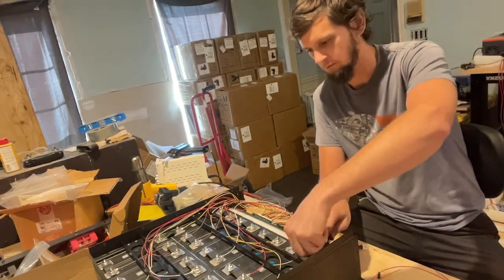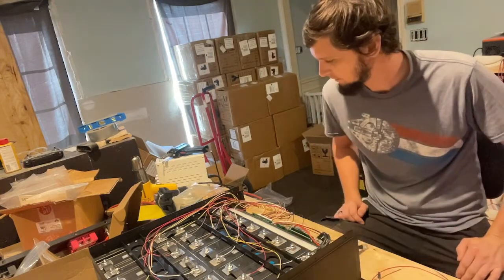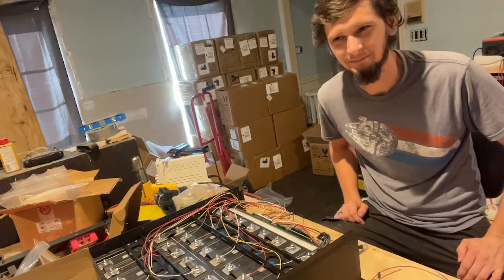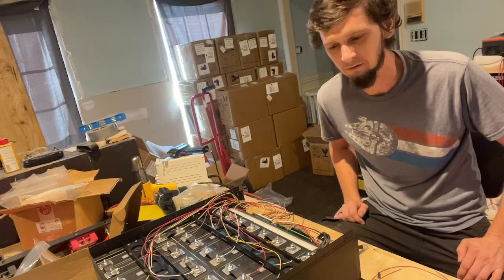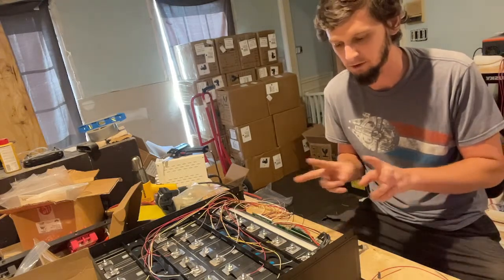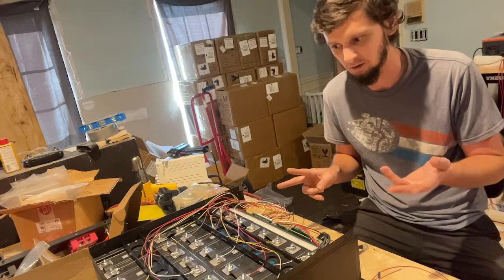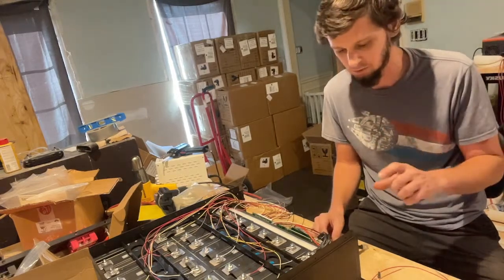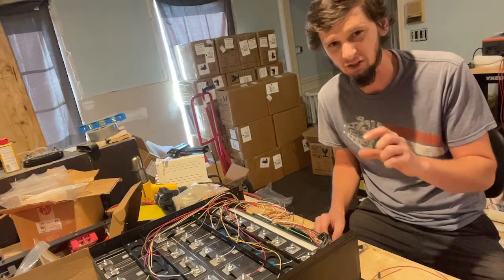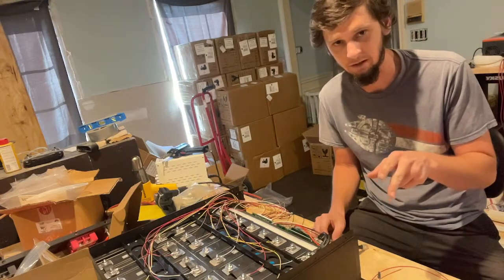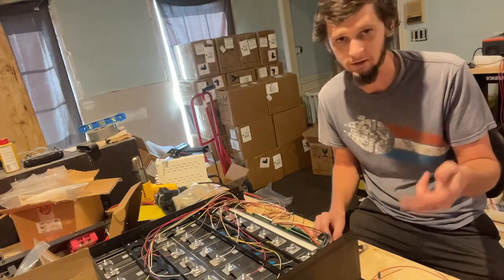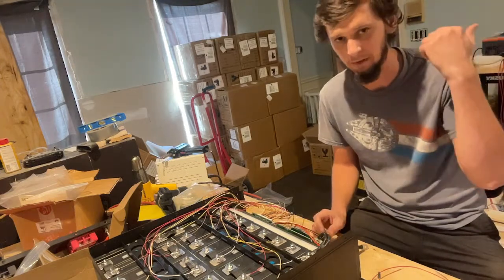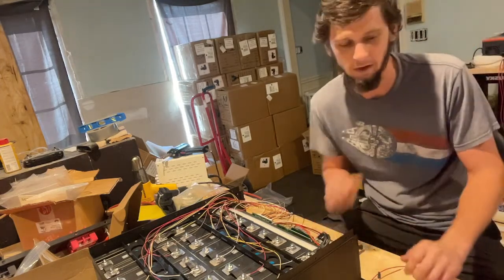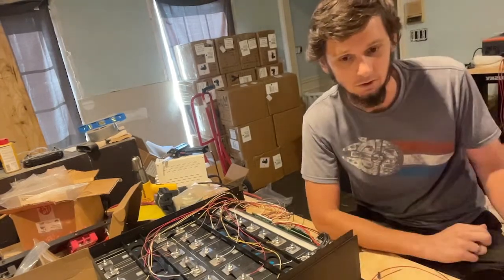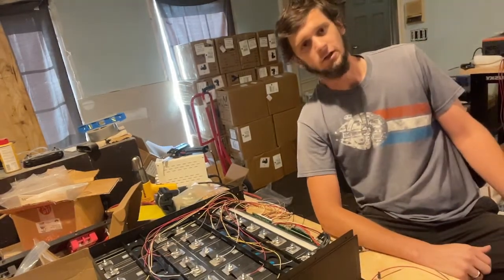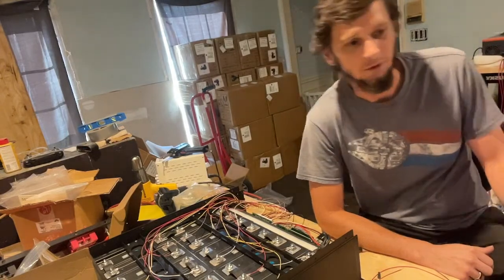I like that. I always try to make it so I don't have to run wires straight off the BMS for very long before hitting something. So normally I'll run a 3/8 stud—the BMS connects to the stud, and then I can run my 2-gauge, 4-gauge, whatever it is, off that stud to the bus bar or inverter. But a bus splice works too, especially for a stationary system where you just need to get back to the main bus bar.